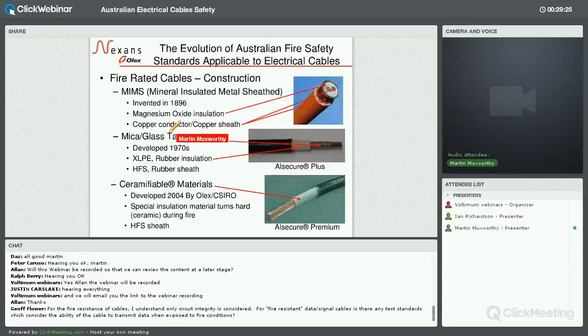The next development or innovation in fire-rated cables came in the 1970s, when I think people looked at alternatives from the MIMS cable, and it involved the use of mica tape. Mica and glass tapes wrapped around the conductor served as a simple means of ensuring that the conductor would remain insulated in a fire condition even after all of the, say, PE or sheathing materials burnt off, because at the time there weren't any special materials that would resist fire in the way that's required during a circuit integrity test.